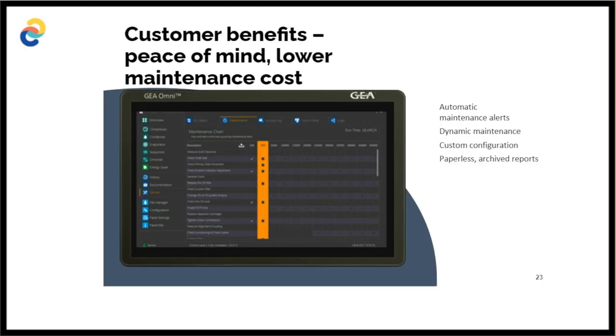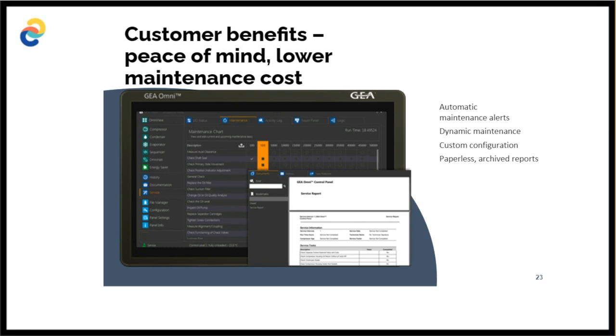But Omni is more than that. In terms of the compressor, it's really looking at giving customers peace of mind. So also lowering things like maintenance costs. So we look at features like automatic maintenance alerts, dynamic maintenance, which means we're constantly looking at the operation of the compressor over a period of time to see if there are any small changes that are occurring that might need some attention. It's very configurable, so the customer can actually see the data that he wants to look at. And there is everything available within the Omni Control as to what's happening on your compressor. And paperless reports. So consequently, if we need a service report, or we want to check when the last service was done, or see what the engineer actually found, if he made any notes, that can all be stored on the Omni Controller.